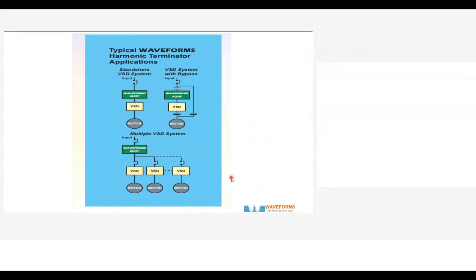This is a diagram to show how these filters can be installed along with one single VFD motor or with multiple VFDs and motors. Suppose you have many VFDs in one panel, you can have one common filter rated to the total capacity, adding the current rating of all the motors and VFDs.